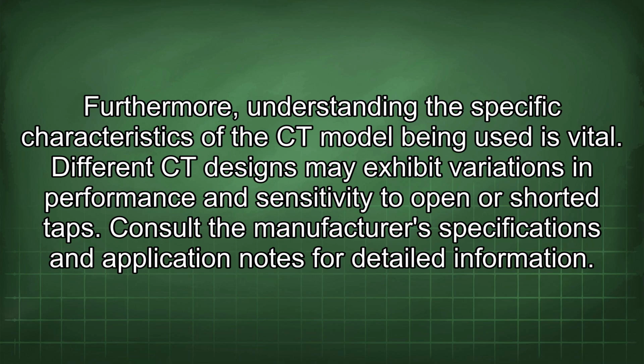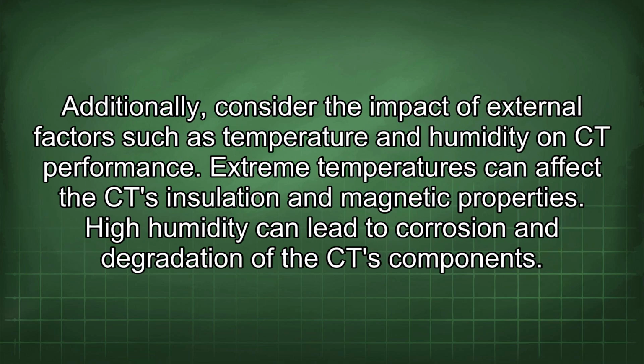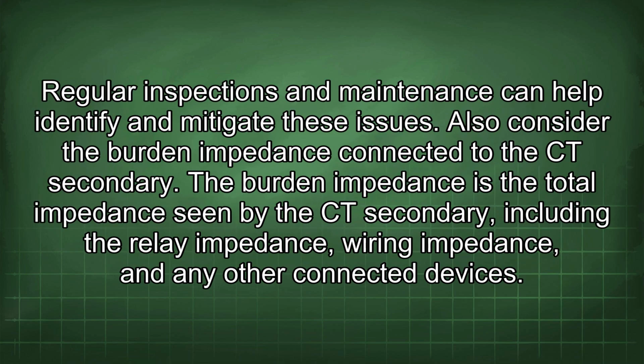Furthermore, understanding the specific characteristics of the CT model being used is vital. Different CT designs may exhibit variations in performance and sensitivity to open or shorted taps. Consult the manufacturer's specifications and application notes for detailed information. Additionally, consider the impact of external factors such as temperature and humidity on CT performance. Extreme temperatures can affect the CT insulation and magnetic properties. High humidity can lead to corrosion and degradation of the CT components. Regular inspections and maintenance can help identify and mitigate these issues.